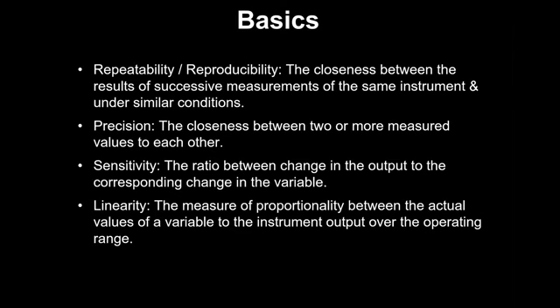The next is basically repeatability, reproducibility. They say that maybe there is a small difference here and there, but in industry they are used interchangeably. When you take multiple readings of the same temperature, how close they are to each other, that is repeatability. So let there be error, suppose plus minus 1% accuracy or plus minus 0.25 accuracy, but for the same water, if you dip that thermocouple and take the reading, is it showing the same reading every time, or is it showing a different reading every time? Without changing the temperature, if you just dip the instrument, take it out, dip it again, whether they show the same temperature, the same value or not, that is the repeatability of the instrument.